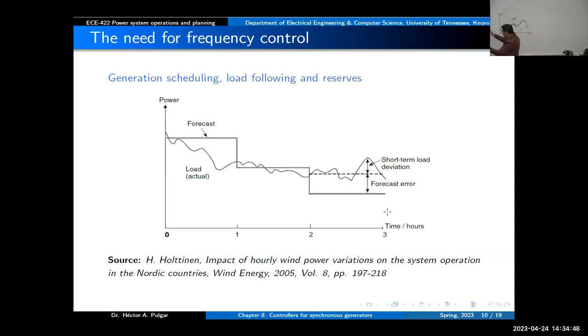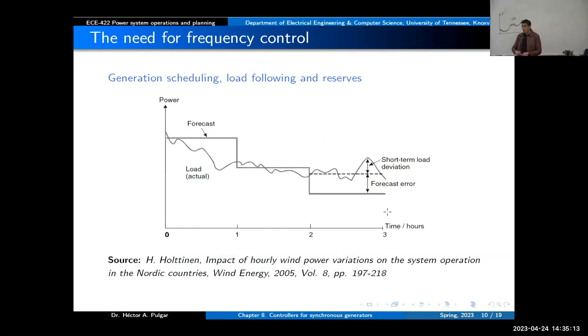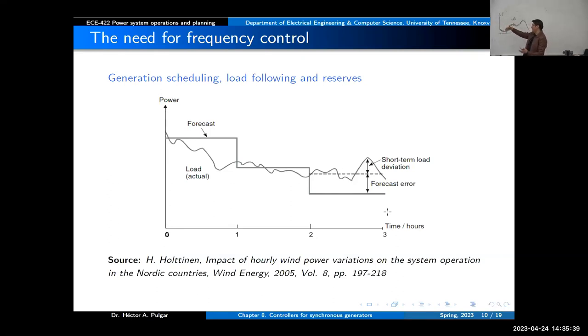For longer-term operation in the system, here we have a graph over three hours. You need to forecast the power demand in the system and anticipate what generation you will have. As mentioned before, we need to deal with the problem of unit commitment — it will be cheaper to turn some generators off to minimize cost. You will do this forecast and define which generators will be connected at different periods of time. The actual load will change and our forecast will not be perfect, so to deal with this issue we need something very important: the reserve.